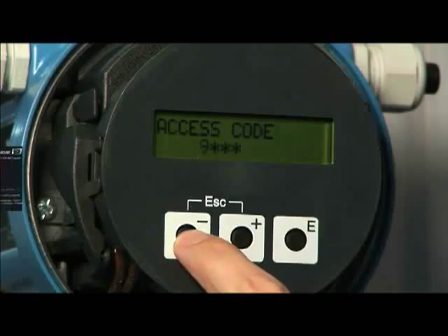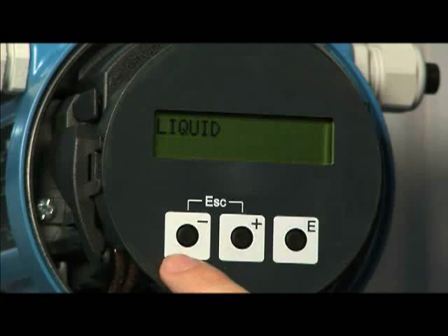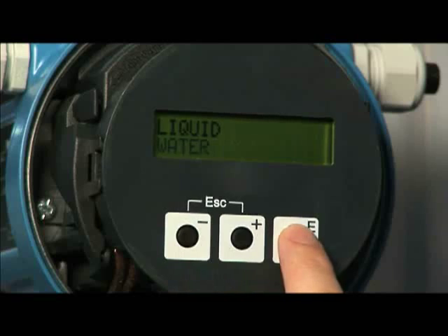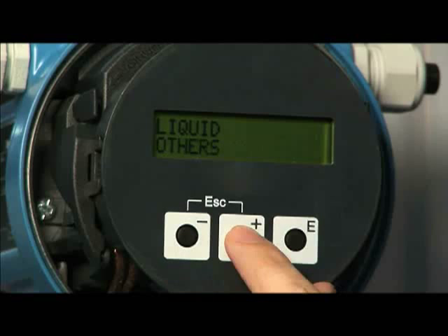The first programming change requires an access code for which the device model number is the default. Then enter the liquid being measured. Various options are available. If your particular liquid is not listed, simply choose the option Others.